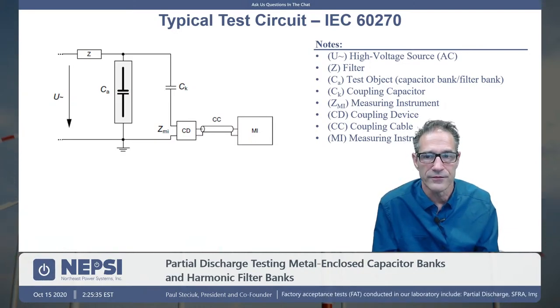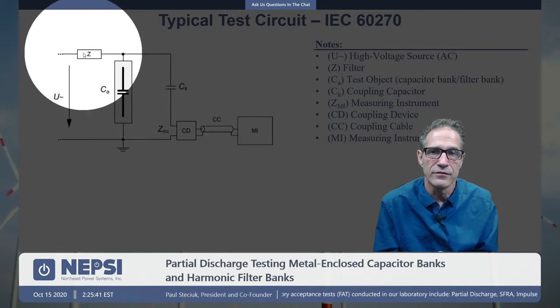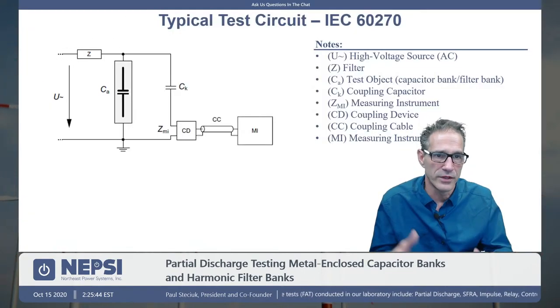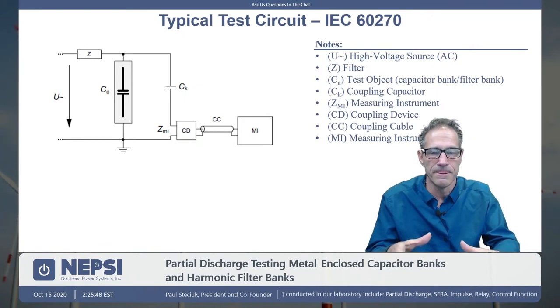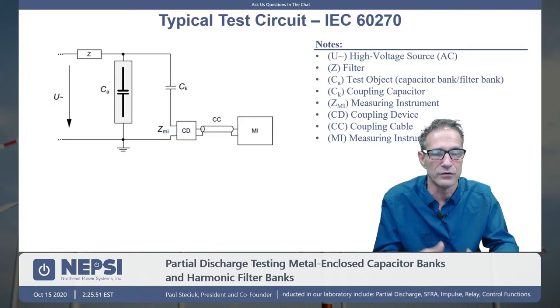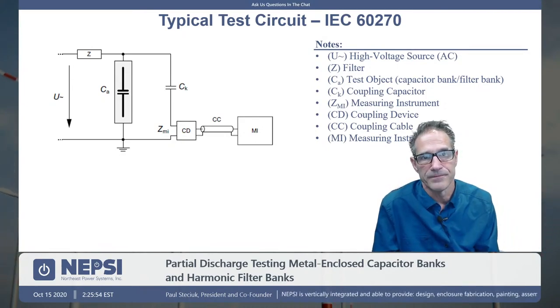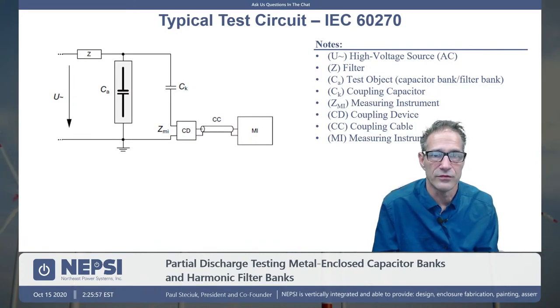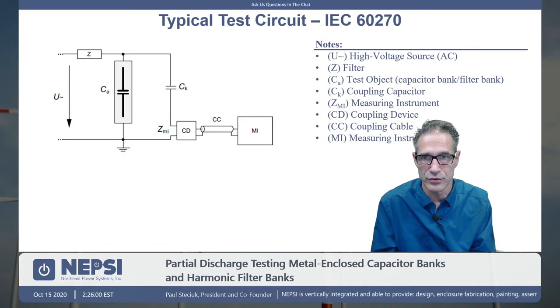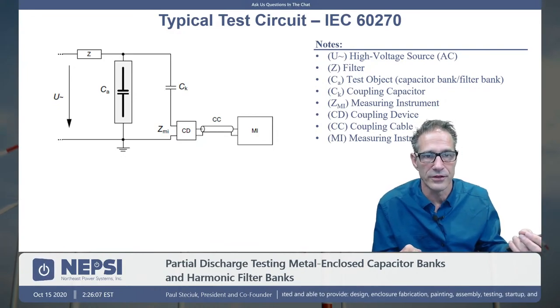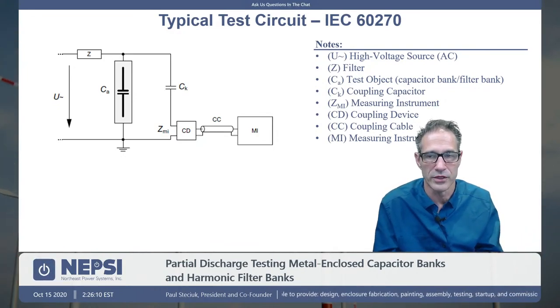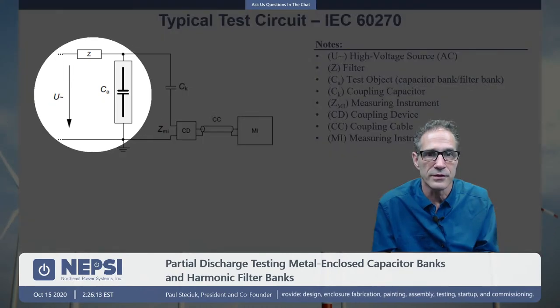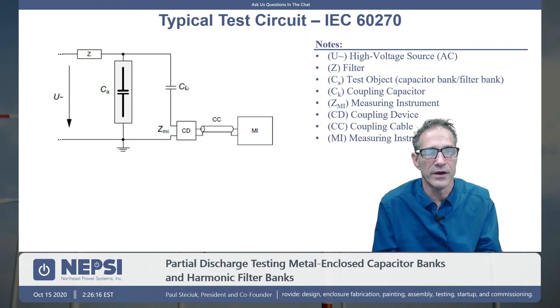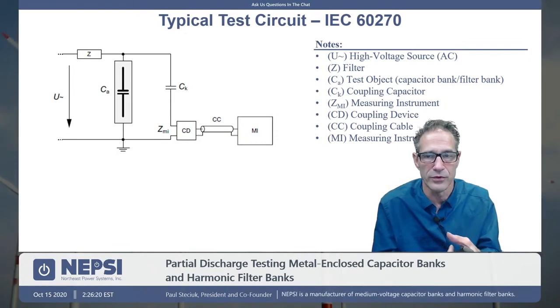So a typical test setup, and again, this is from IEC 60270, and incidentally, the IEEE standard follows this standard. We have this value Z here, which is a filter. So we take our high voltage test set, we put a filter on it, and that filter is basically giving us a clean voltage supply. The high voltage supply, incidentally, is AC. CA is the test object. This would represent our harmonic filter or our capacitor bank. And we remove the capacitors during the test. The capacitance is very significant otherwise, and we would not be able to test the equipment. CK represents the voltage divider and also the coupling capacitor. That's all built into our system.